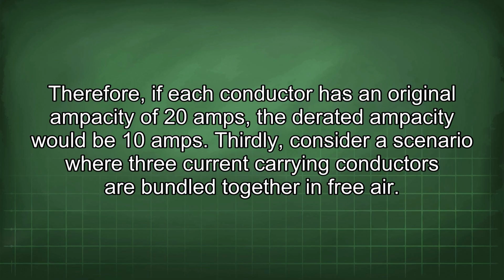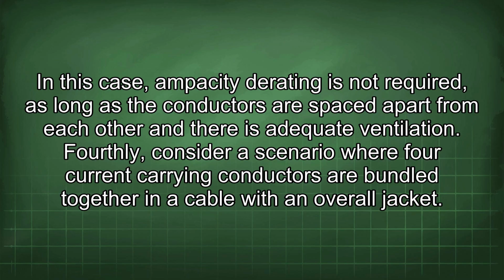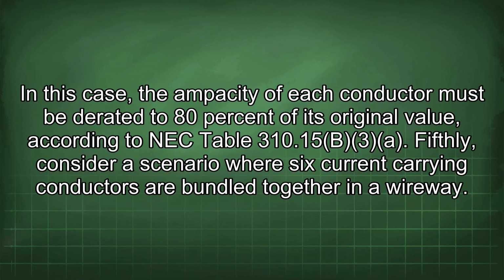Thirdly, consider a scenario where 3 current-carrying conductors are bundled together in free air. In this case, ampacity derating is not required, as long as the conductors are spaced apart from each other and there is adequate ventilation. Fourthly, consider a scenario where 4 current-carrying conductors are bundled together in a cable with an overall jacket. In this case, the ampacity of each conductor must be derated to 80% of its original value, according to NEC Table 310.15(B)(3).